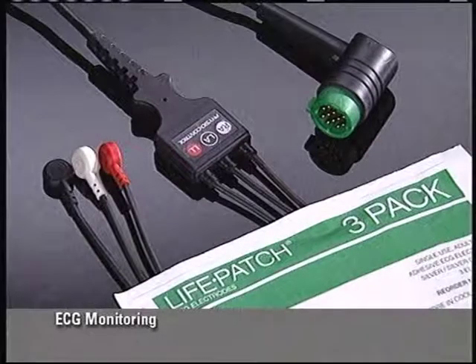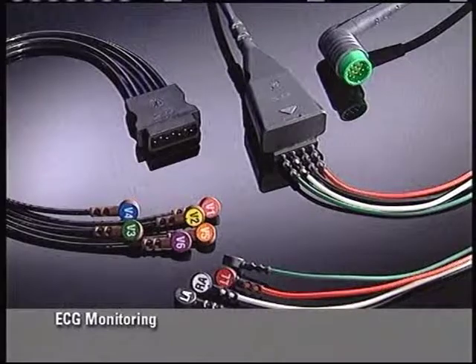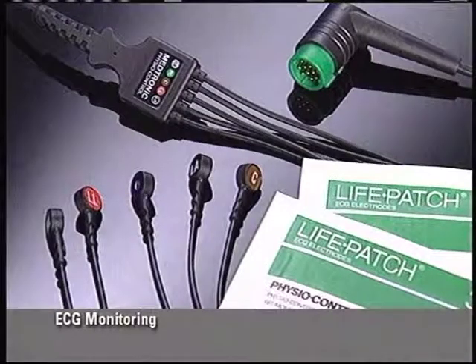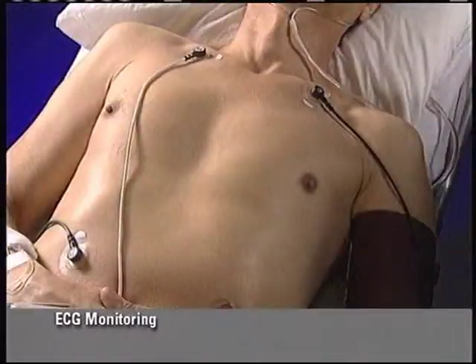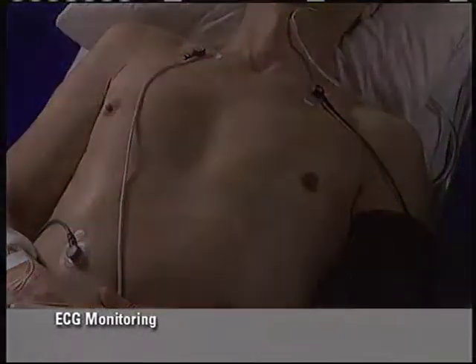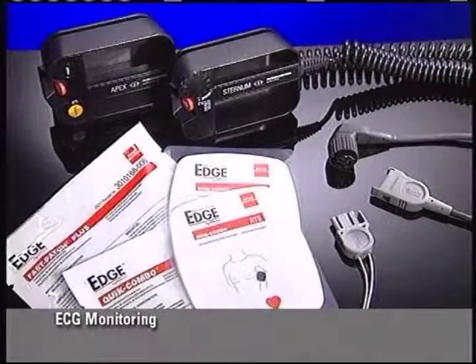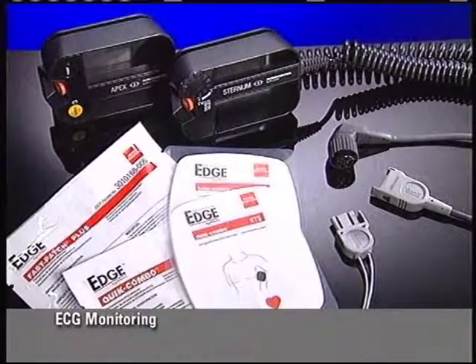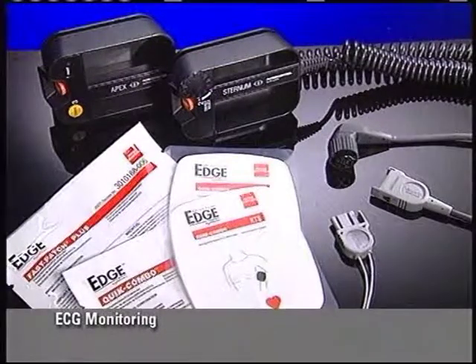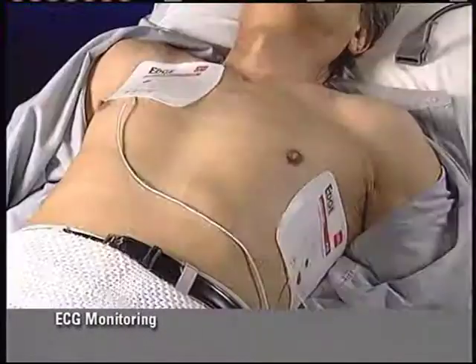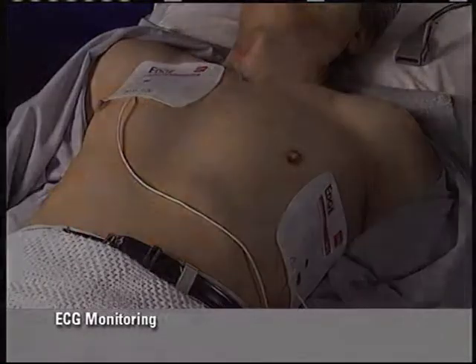The patient's ECG can be monitored with a 3-lead, 12-lead, or 5-wire cable. This is referred to as ECG leads monitoring. The ECG can also be monitored with standard or hard paddles, or the quick combo therapy cable and electrodes. This is referred to as paddles lead monitoring.